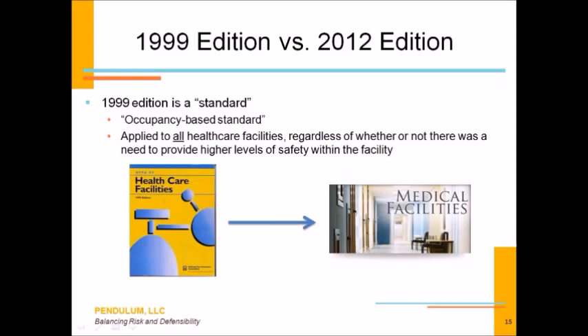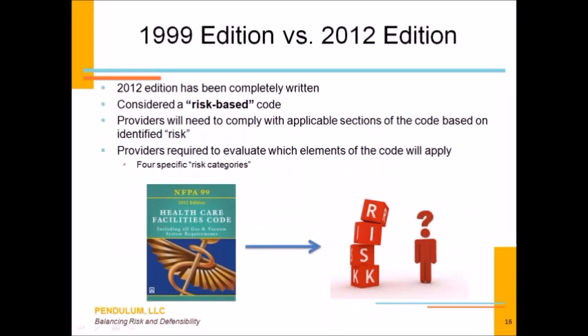The big difference between the 1999 edition and the 2012 edition of NFPA 99 is that the 1999 edition was an occupancy-based standard. That means that it was a standard that applied to all healthcare facilities. I remember trying to fit the elements of 1999 into a nursing home, and it was somewhat difficult because most of the applicability of the 1999 edition really didn't apply to a nursing home. There were no surgical suites. There were no suites in general. There were no radiology departments or other technical elements.